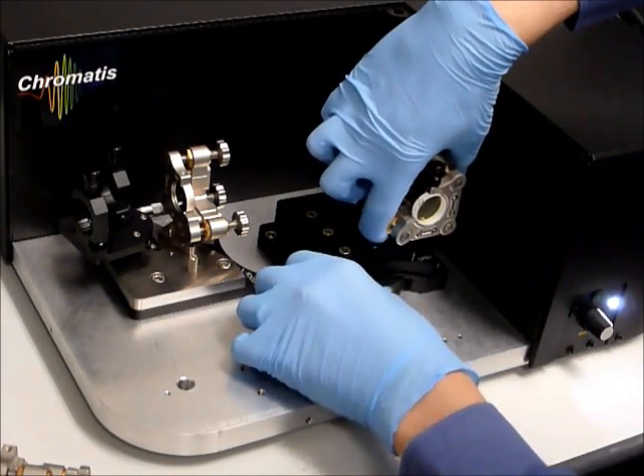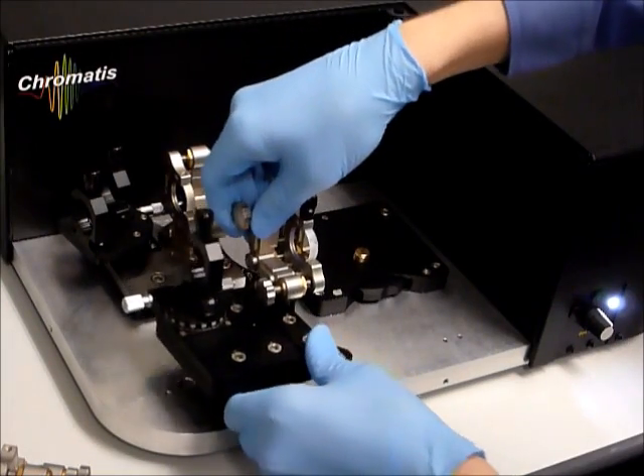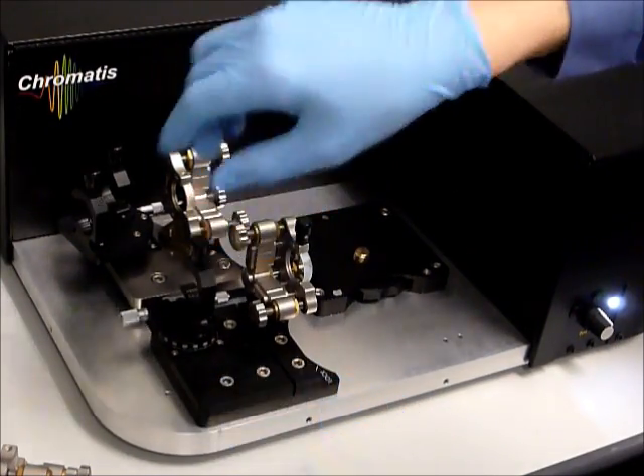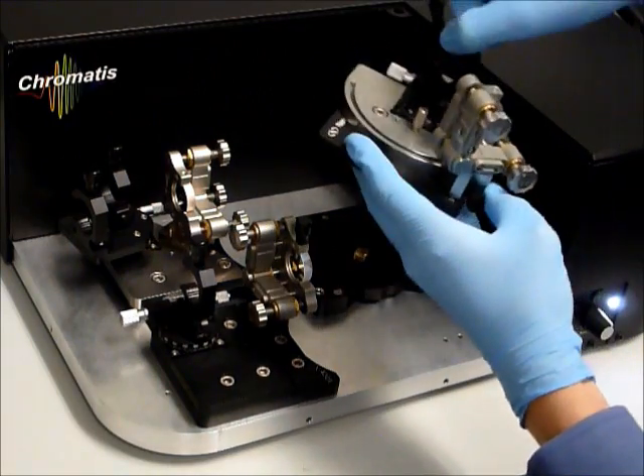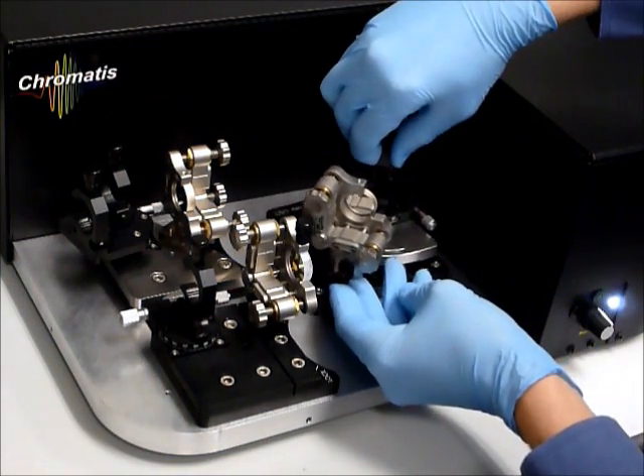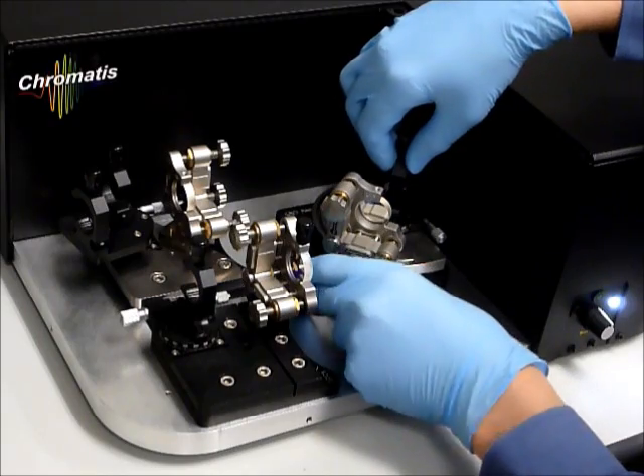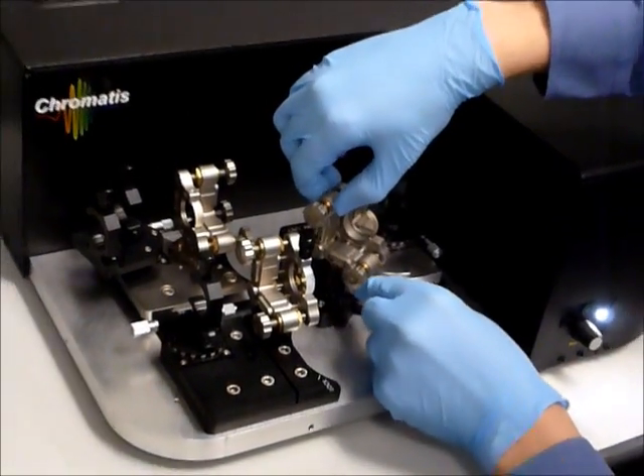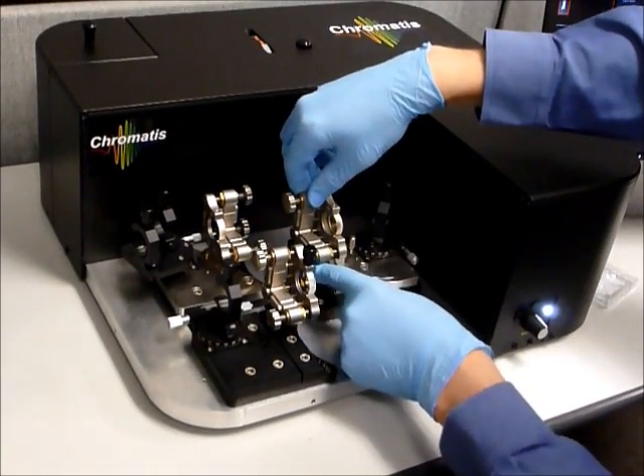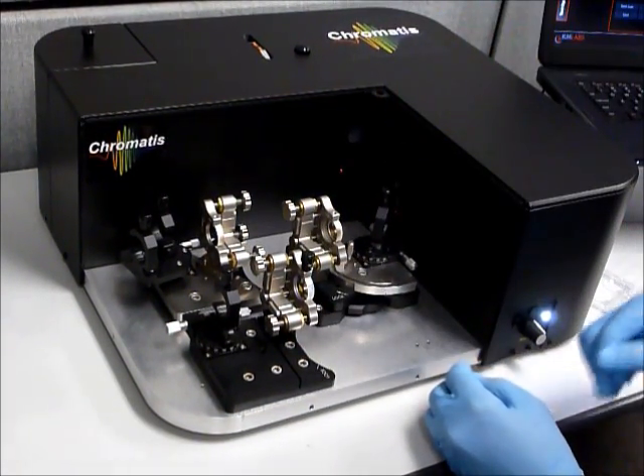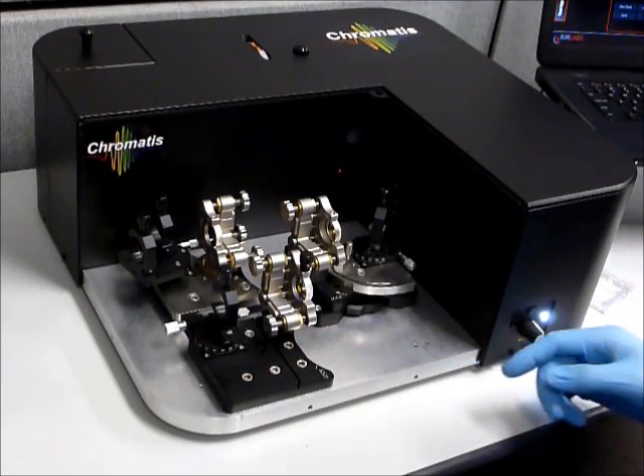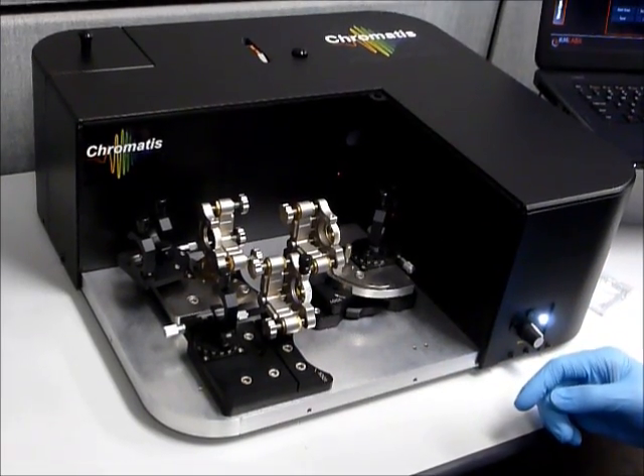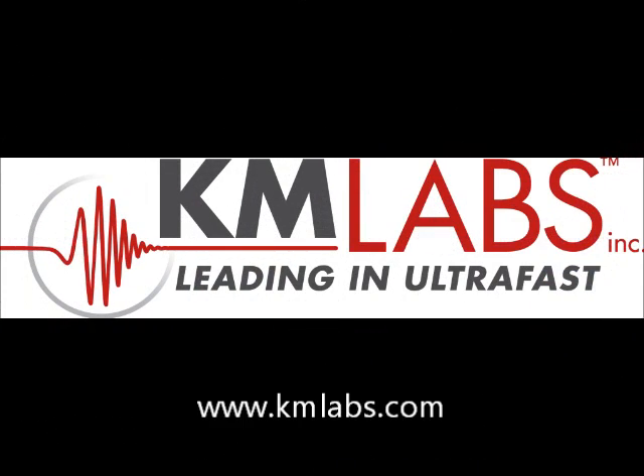So we can just remove the zero degree fixture, and put the angle measurement fixture in, and lock it in place. We're ready to do angle measurements. And as I said, this device can do arbitrary angle of incidences on many different platforms. And that, in a nutshell, is Chromatis and how to make a measurement.